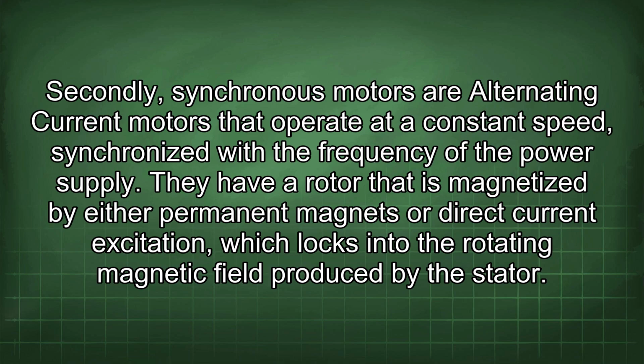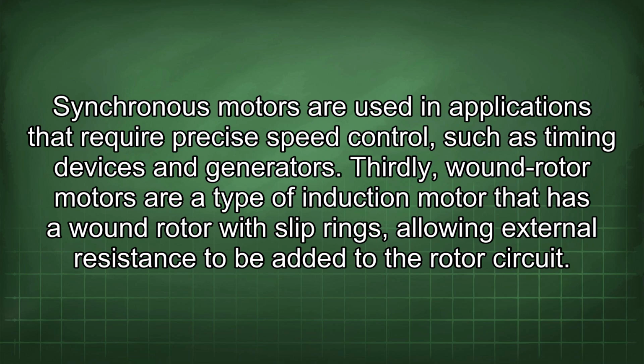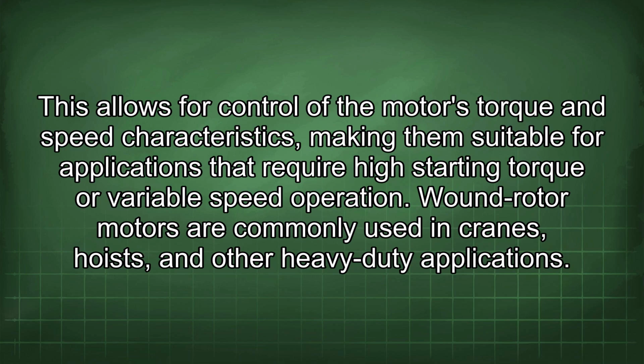Secondly, synchronous motors are alternating current motors that operate at a constant speed, synchronized with the frequency of the power supply. They have a rotor that is magnetized by either permanent magnets or direct current excitation, which locks into the rotating magnetic field produced by the stator. Synchronous motors are used in applications that require precise speed control, such as timing devices and generators. Thirdly, wound rotor motors are a type of induction motor that has a wound rotor with slip rings, allowing external resistance to be added to the rotor circuit. This allows for control of the motor's torque and speed characteristics, making them suitable for applications that require high starting torque or variable speed operation. Wound rotor motors are commonly used in cranes, hoists, and other heavy-duty applications.